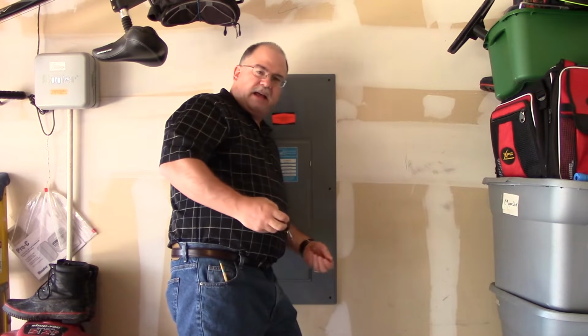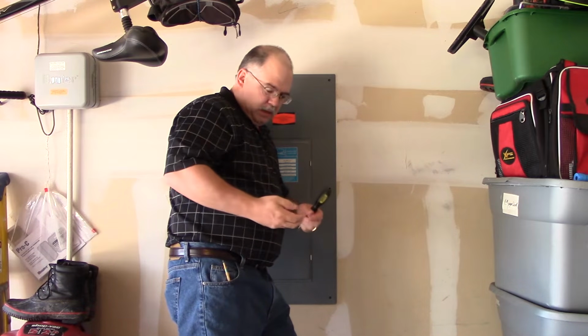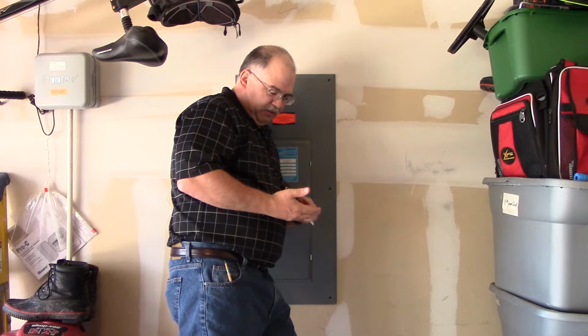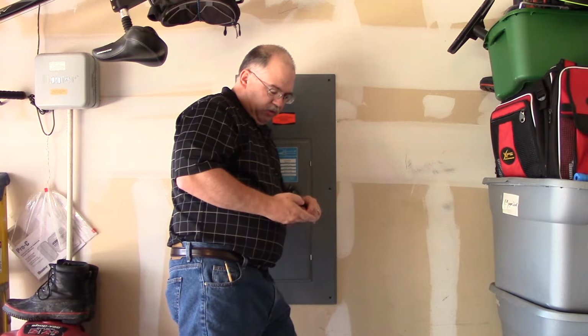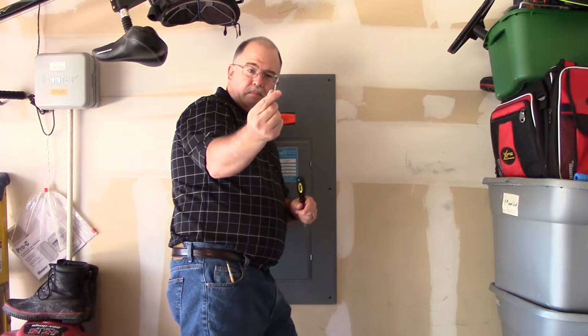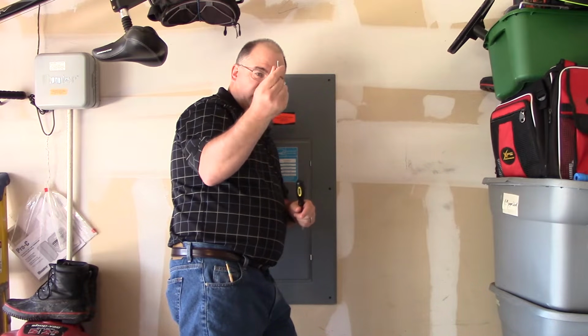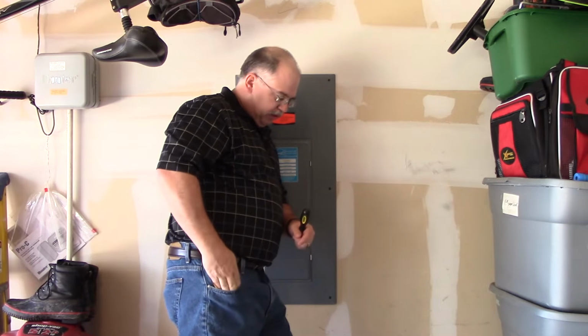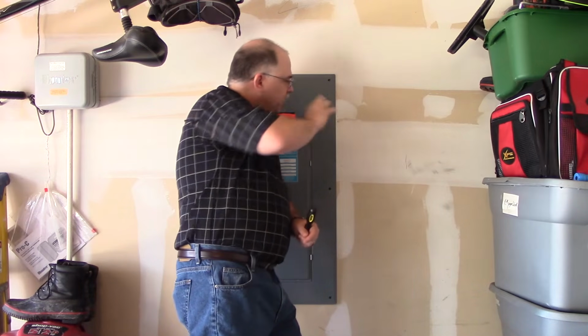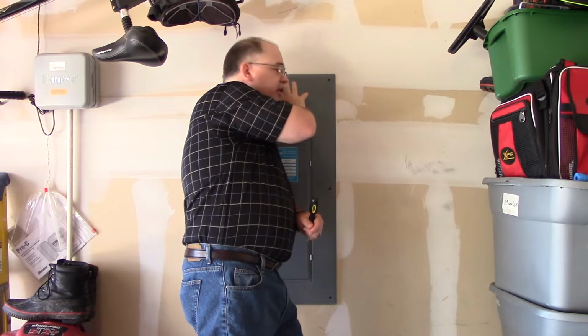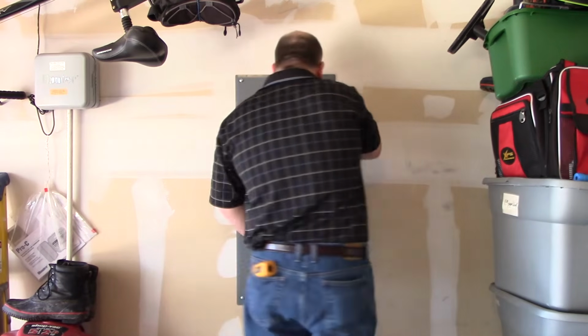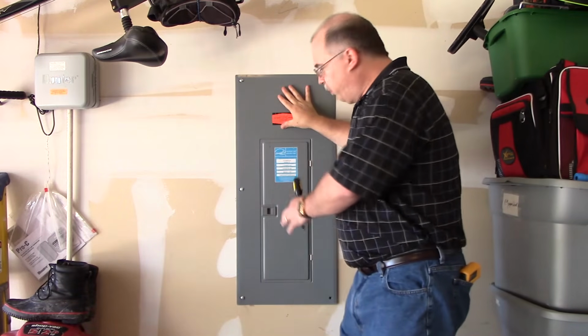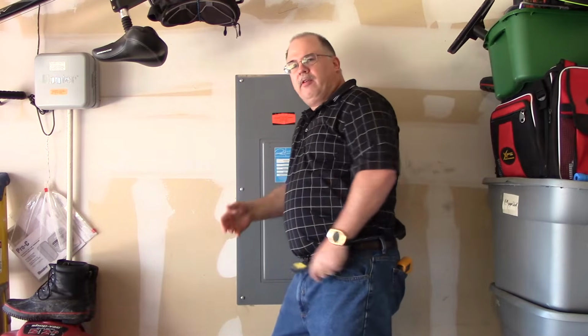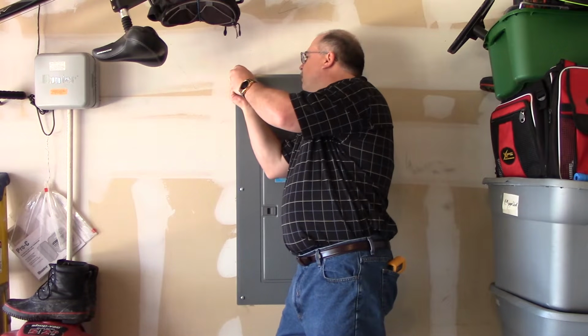Okay, so I removed this side. I'm going to take these screws here. I'm going to look at them and see if I see any signs of arcing on them, anything that looks out of the ordinary. And of course, these screws are a blunt tip screw that's designed to go with this panel enclosure, so we're good there. Put them in your pocket. Support this panel cover and then shift over, keeping your hand against it to support it. Now put your shoulder against it on this side and remove the screws on this side.